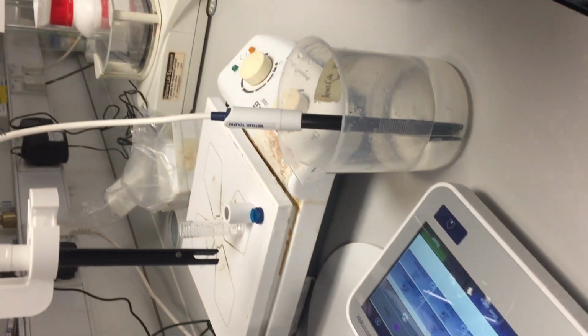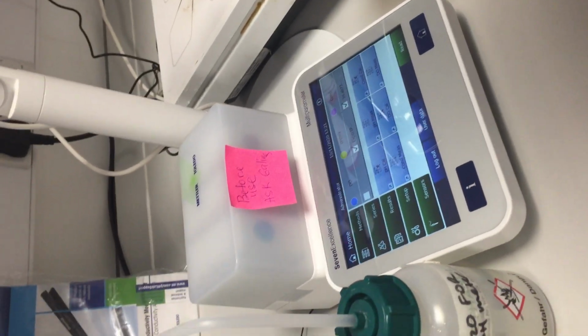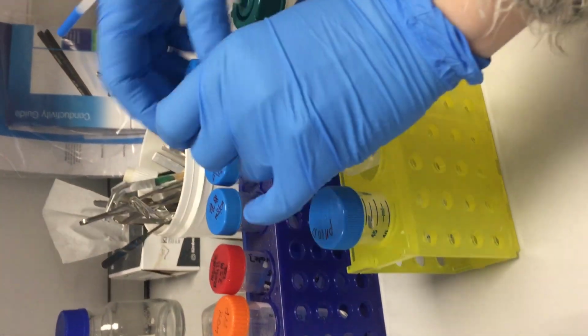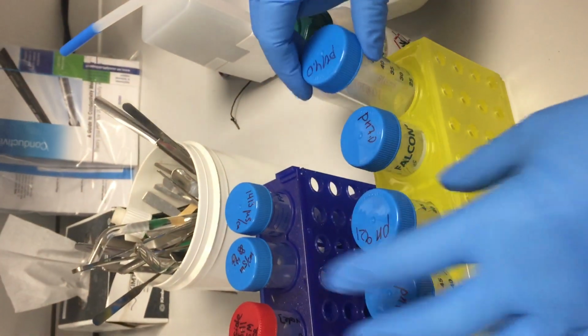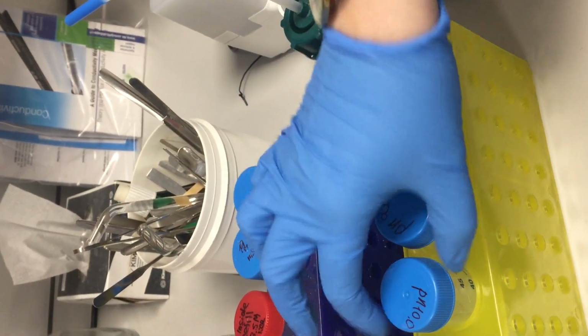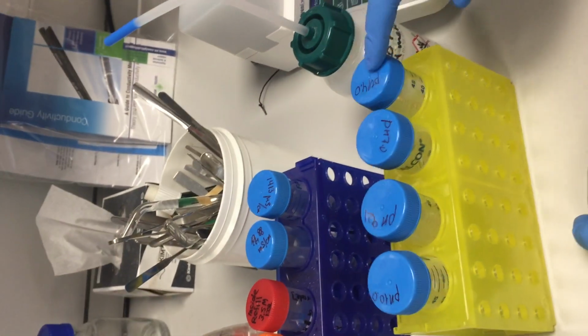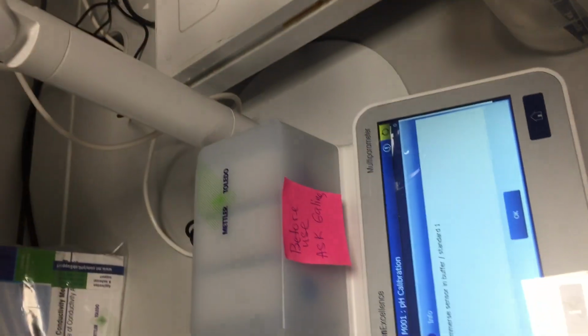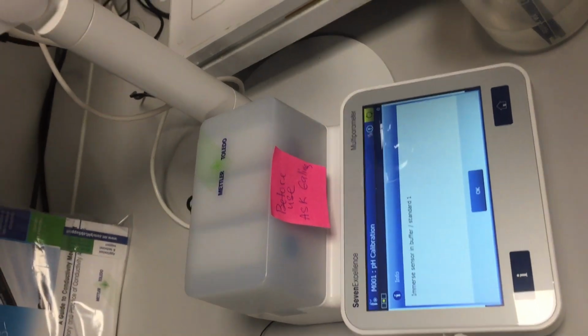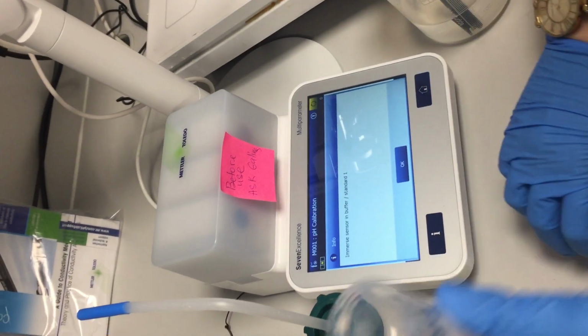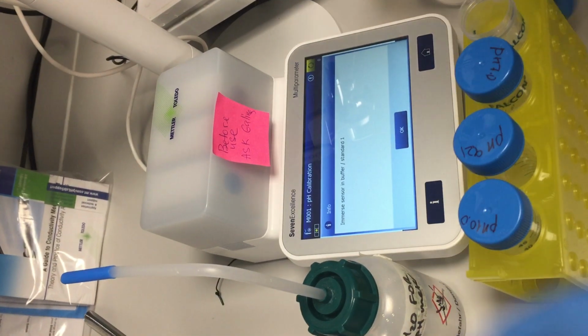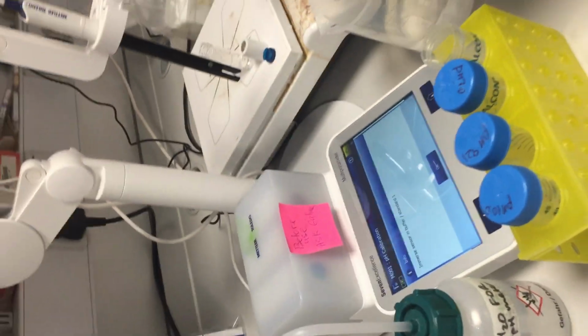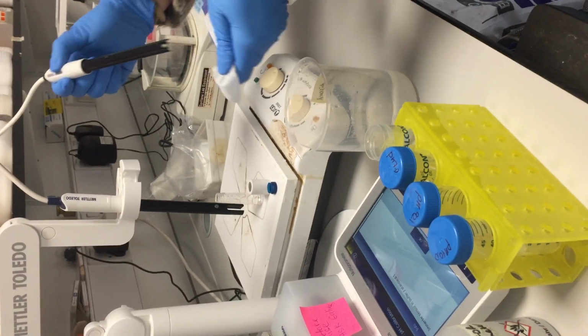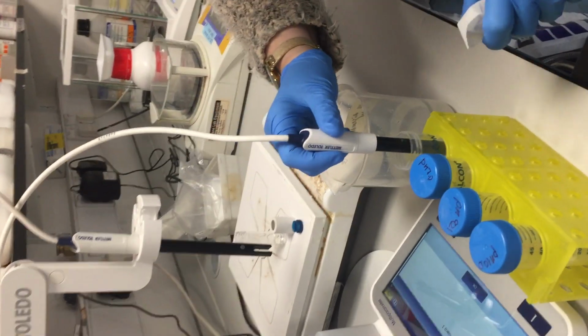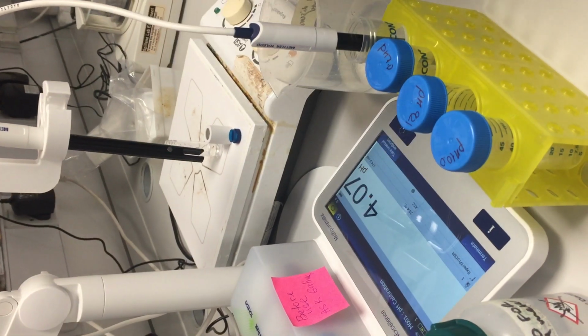So for pH calibration, we have 4 different calibration solutions. Solution 4, solution 7, 9.21 and 10. For calibration we are using 4, 7 and 9.21. So to do the calibration we are going for pH calibration, and it is asking please immerse in the first buffer. So this is what we are doing. We're just taking our electrode, putting it in the first buffer and pressing OK.